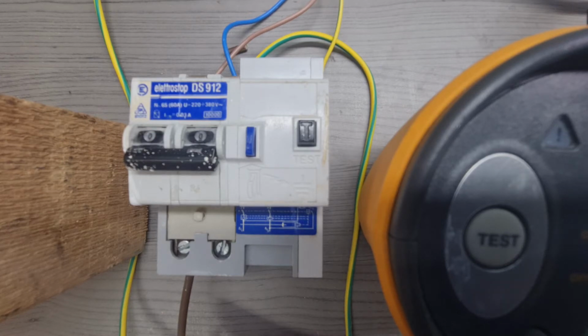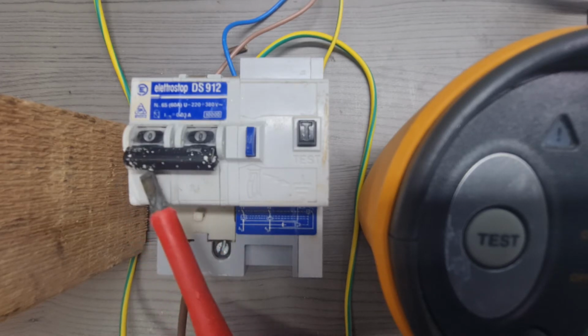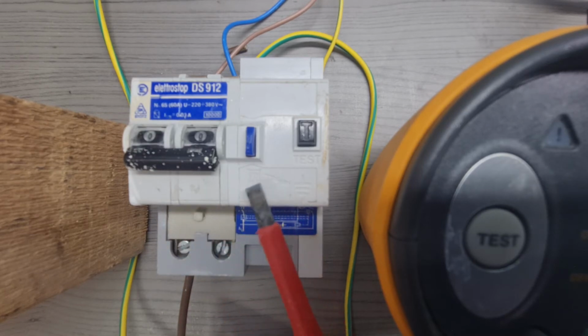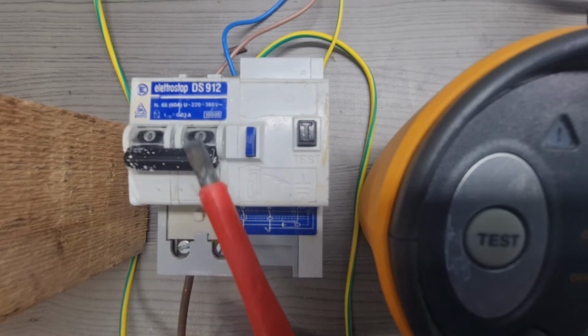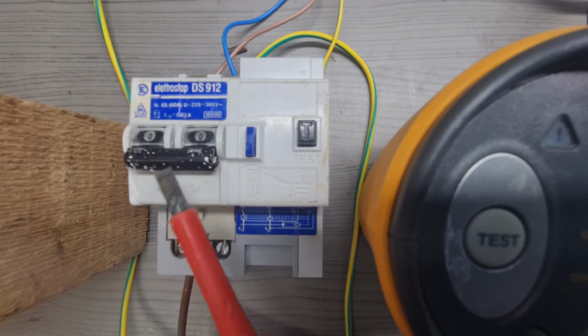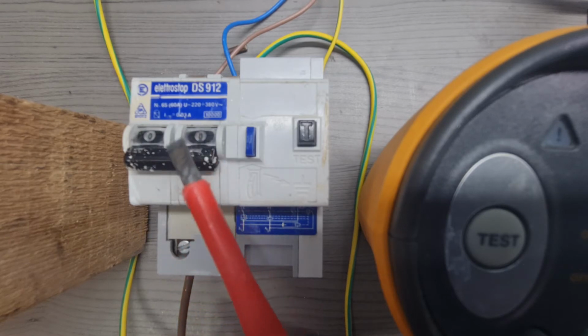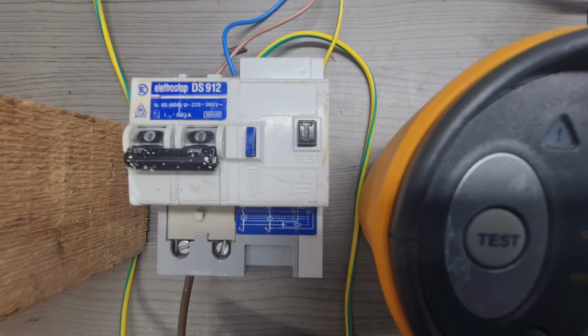DS912. As we can see, as an RCD, it is quite a large device, and basically it looks like a main switch with a disconnection mechanism. The rating is at 60 amperes and it has a nominal tripping current of 30 milliamps.